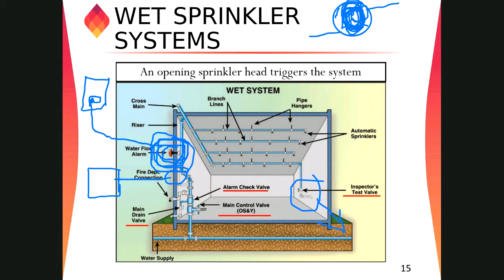So here we have the basic arrangement of a wet pipe sprinkler system, right? This is the schematic from the underground network. We are getting water into the system at this location. We have the gate valve, the water supply control valve, and then we have an alarm check valve. And from the top, we have a fire department connection coming from this line.